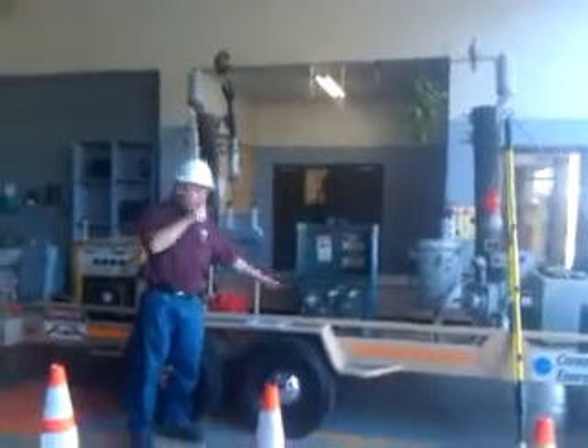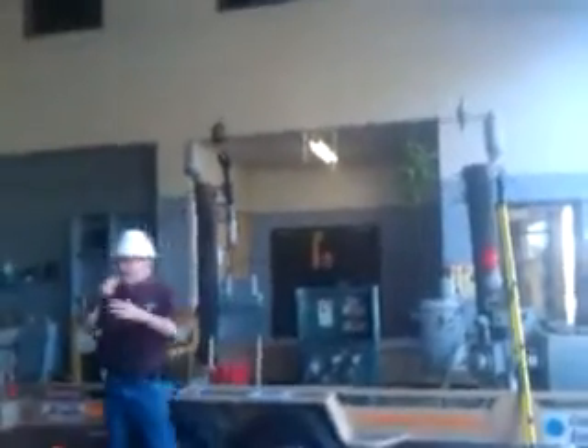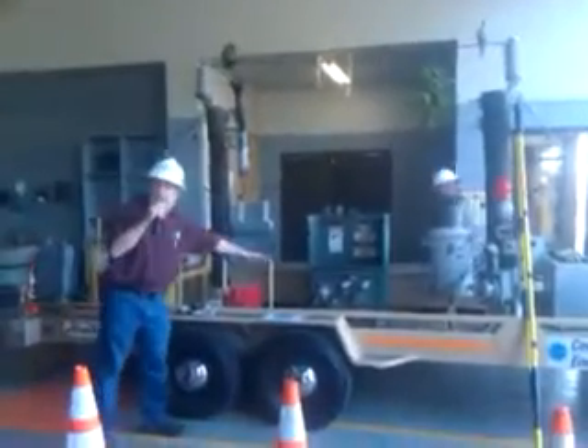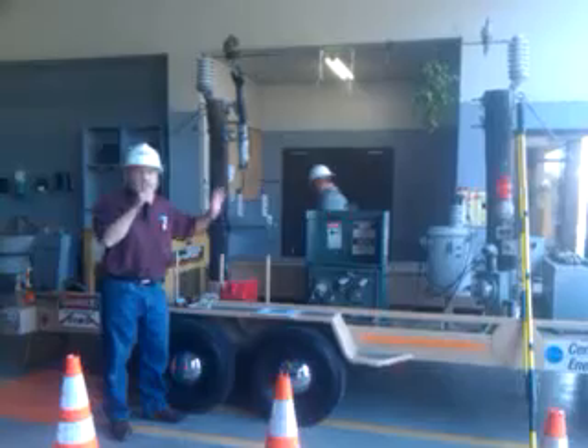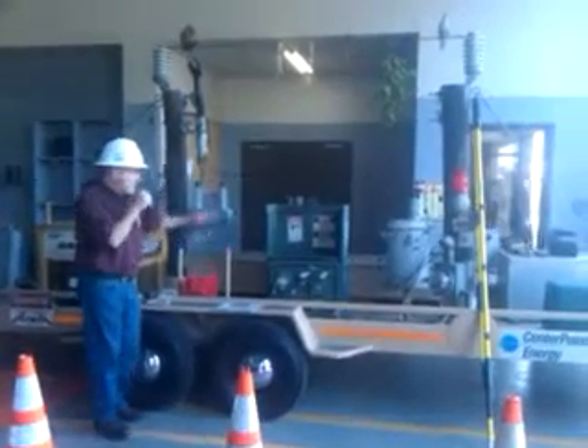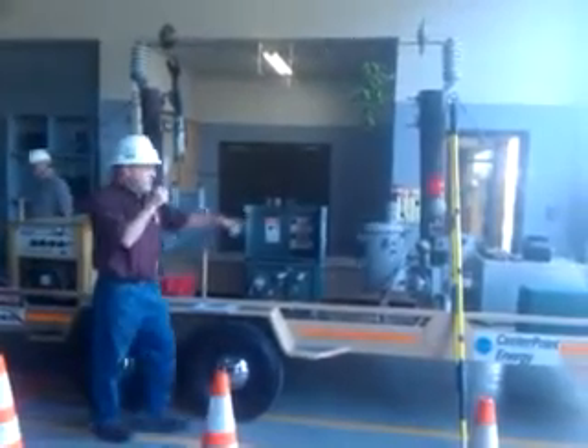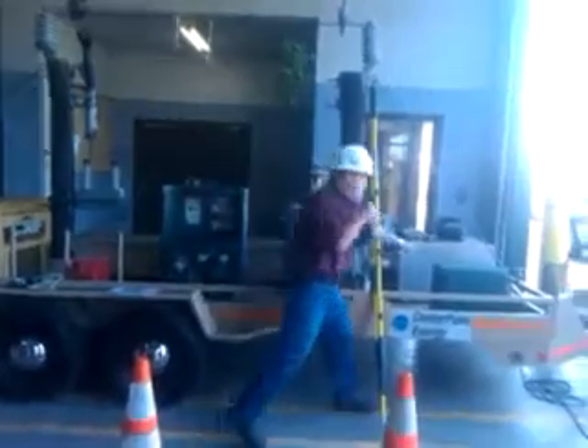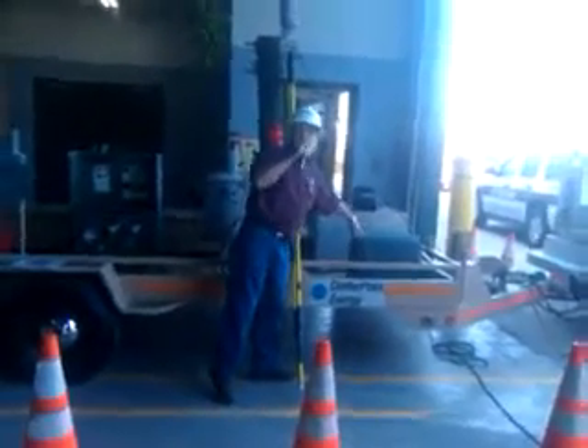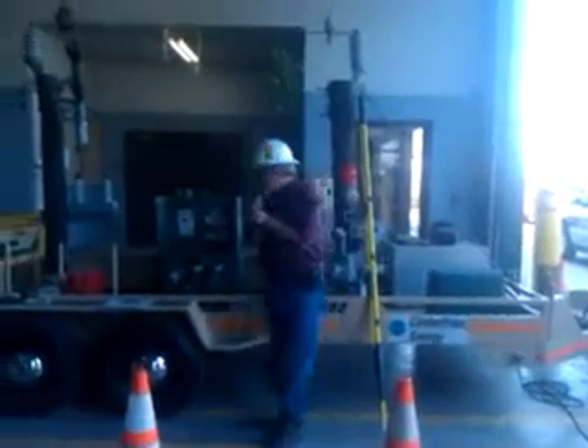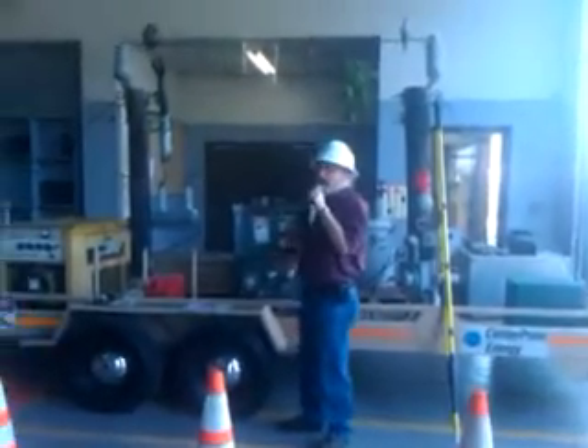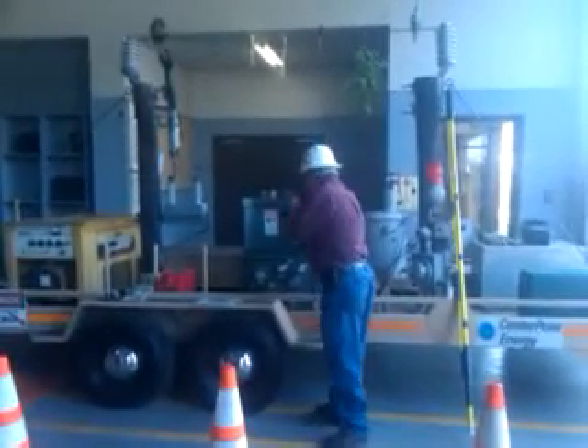920 volts in this box. So again, if water gets up in there, you talk about walking towards it, you might get some tingling. If it's on fire, the equipment's already shot, we don't want it back. Just let it burn. Do not spray water on this. Don't try to cut the lock and get in it. This is the secondary pedestal. Again, there can be 120, 240 volts in here. And again, this can be 7,200 up to 19,920.